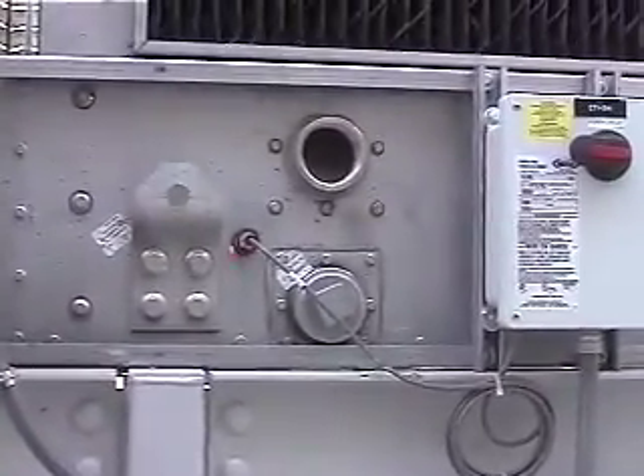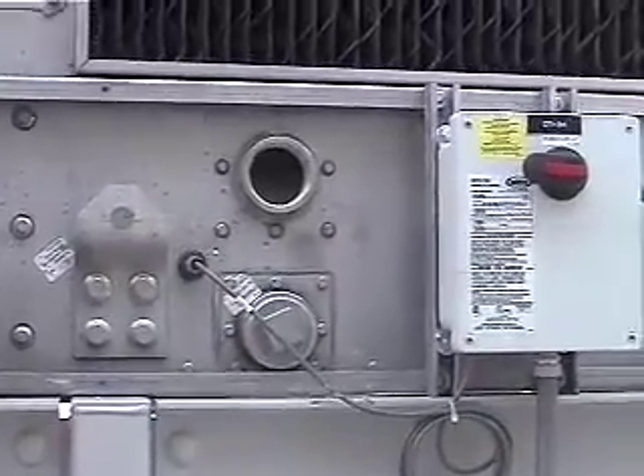Right there. Basin heater element, probe with low water cutoff, and control panel, disconnect switch for the basin heater. Again, control panel for the water level switch. The probes are inside here at various levels for the makeup and the low and high water cutoff. Or actually it's signal. Right up here is the water inlet from your building.